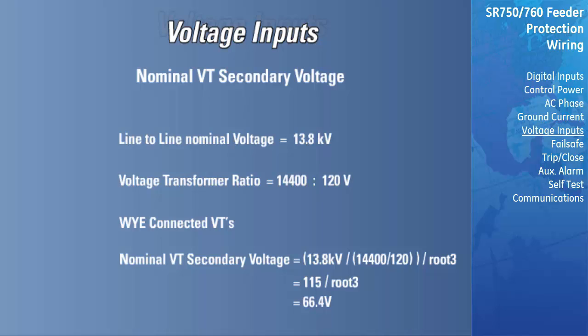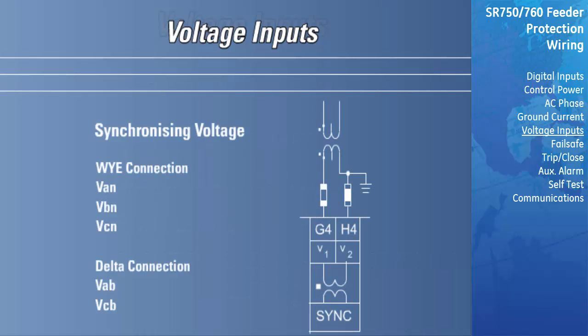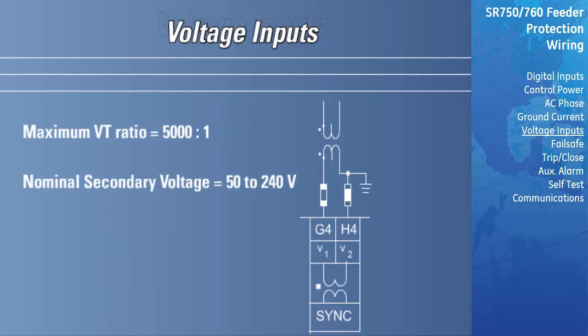The relay will compare the voltage amplitude and phase angle, as well as the frequency of the line VT to those metered on the bus VTs. Based on the settings programmed, it will then allow or block the closing of the breaker. The line VT can be connected as either a Y or delta. The relay must be programmed with the connection that is used to allow for compensation of the phase angle. As with the bus VTs, there is a maximum allowable VT ratio of 5,000 to 1, and the nominal secondary voltage must fall between 50 and 240 volts.